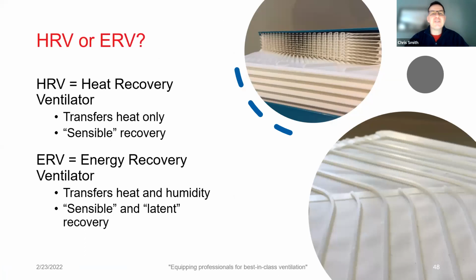Let's talk briefly about HRVs and ERVs. In general, we're talking about energy recovery ventilation, but more specifically, we can talk about a heat recovery ventilator, which transfers heat only. Sometimes this is referred to as sensible recovery, or we can talk about an ERV. An ERV is more broadly talking about energy recovery, and it transfers both heat and humidity. So, if we talk about heat in the traditional sense, we're talking about sensible recovery. Humidity, we're talking about latent recovery. Latent and sensible heat are both parts of enthalpy.